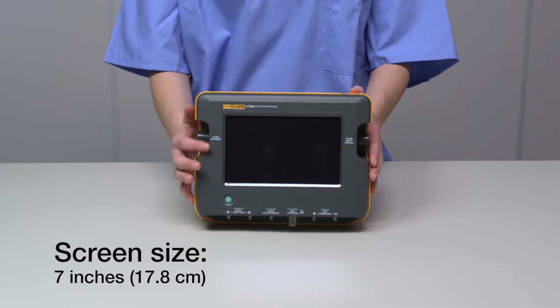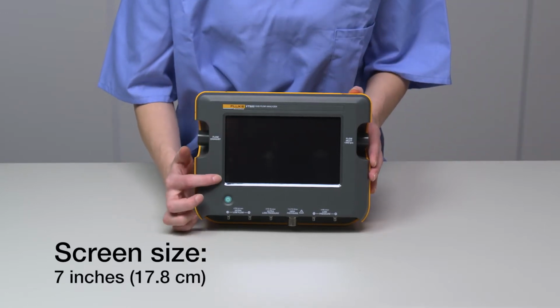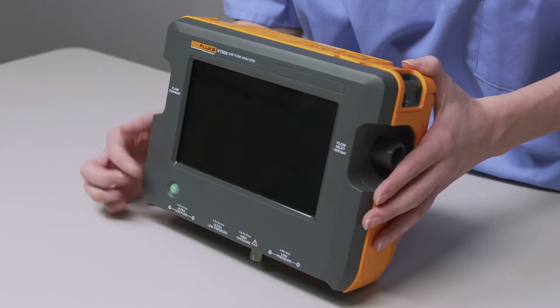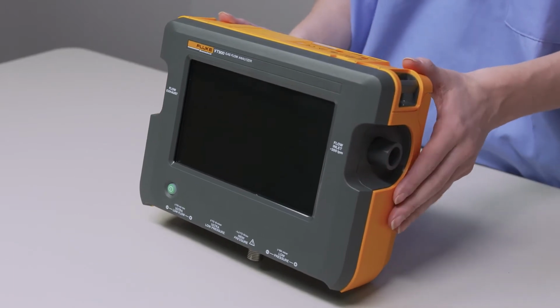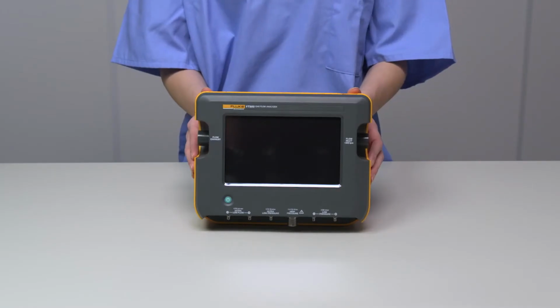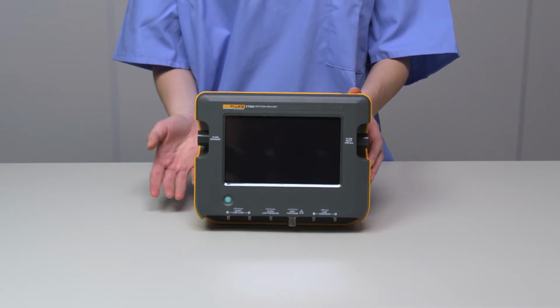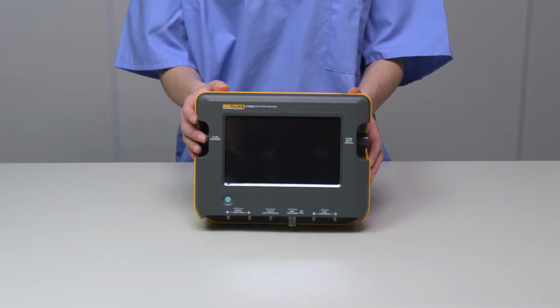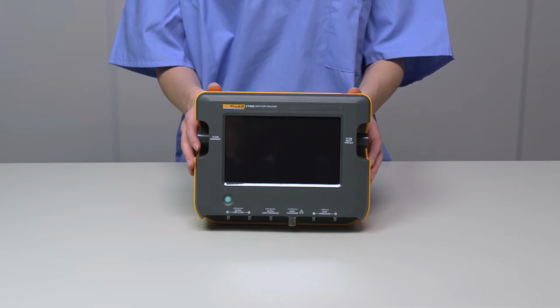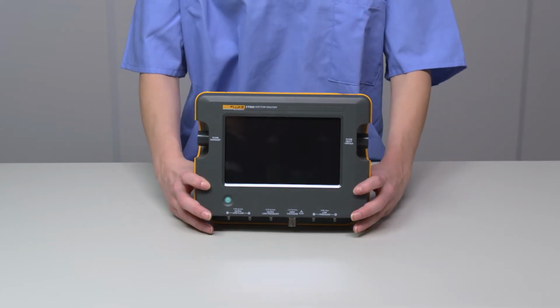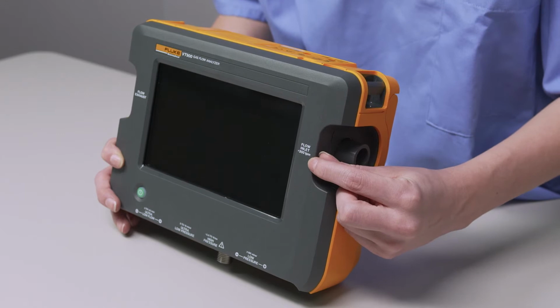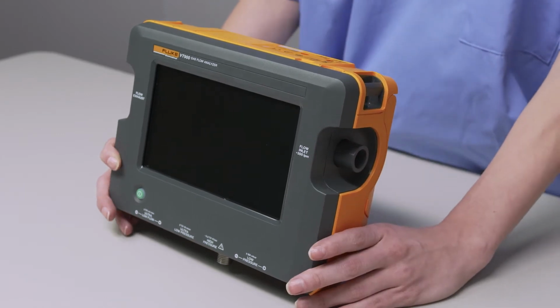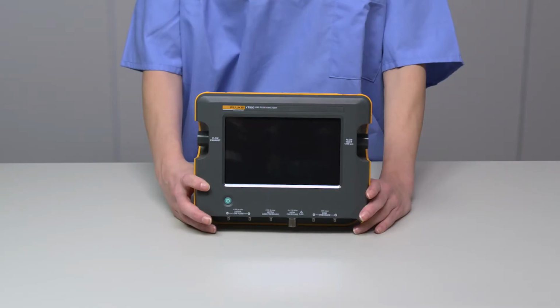Here we have a large color LCD touchscreen, the on button, and a single flow airway channel. This channel has oxygen, humidity, and temperature sensors built in line. It automatically compensates for temperature, humidity, and atmospheric pressure. This channel is full range, plus or minus 300 liters per minute, which streamlines your testing and eliminates the need to hook and unhook hoses to multiple ports for your ventilator testing.